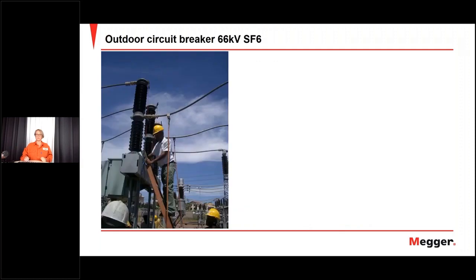And this is the Siemens medium voltage breaker, which is in the metal clad switchgear. We have outdoor breakers. A thing I want to mention here is that you see that they work safe. You can actually see to the left that they have grounded, not only on this side, but on this side as well. And the circuit breaker is actually closed here. So you have a safe situation to connect. But they're actually preparing here for normal timing, classic timing with one side grounded. So they're going to remove one ground before they start measuring. And this is this ABB breaker in Mozambique.